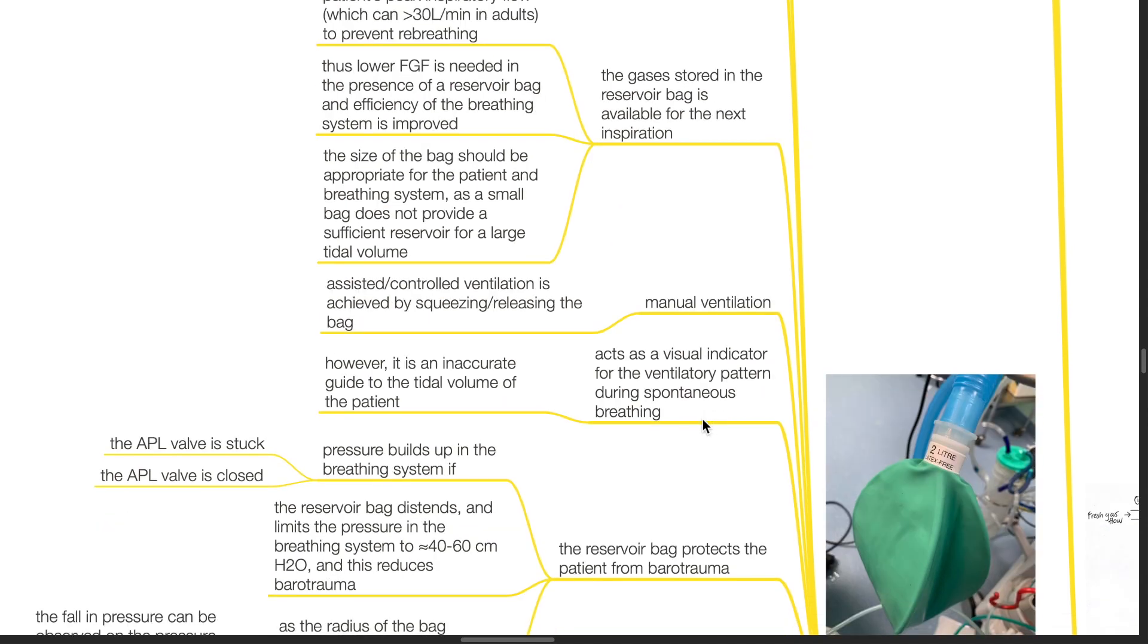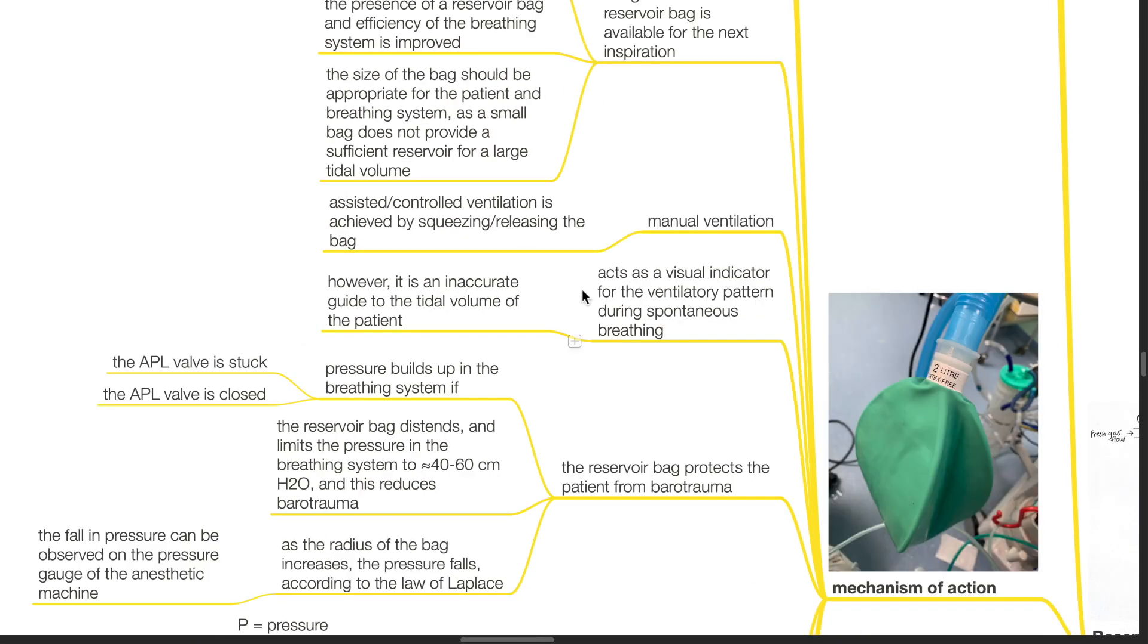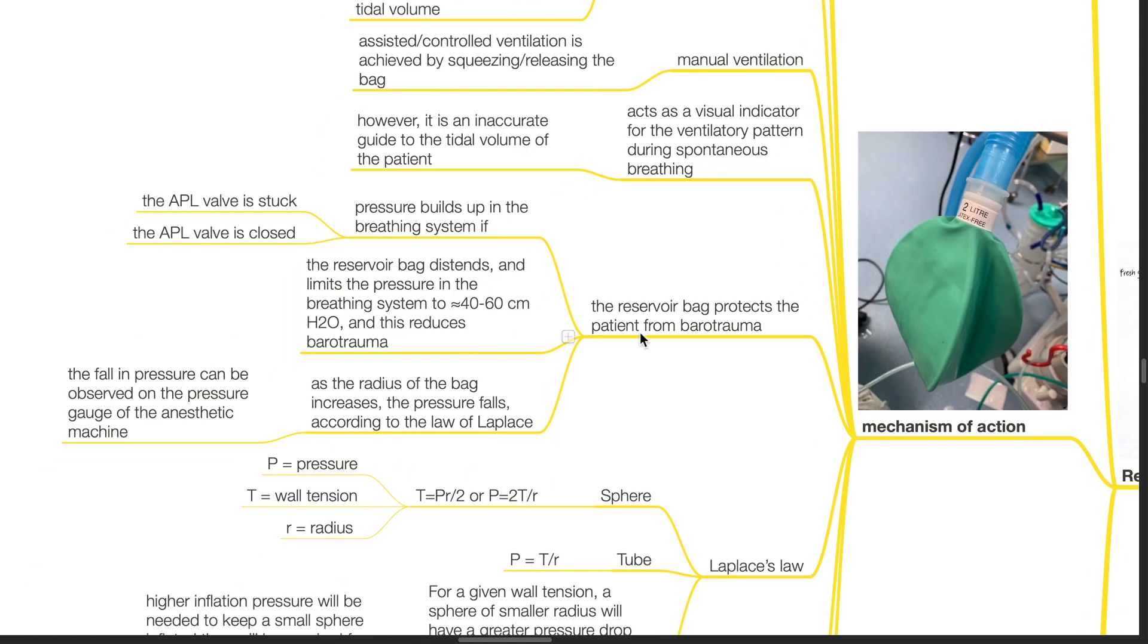For manual ventilation, assisted or controlled ventilation is achieved by squeezing and releasing the bag. The reservoir bag acts as a visual indicator for the ventilatory pattern during spontaneous breathing. However, it is an inaccurate guide to the tidal volume of the patient.